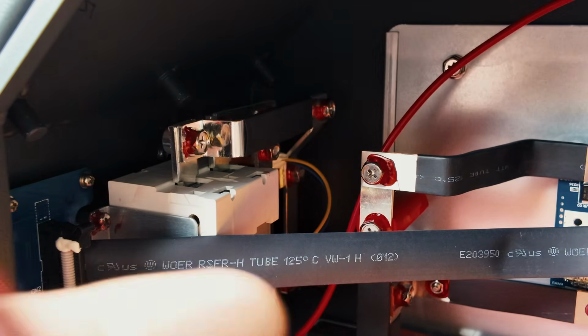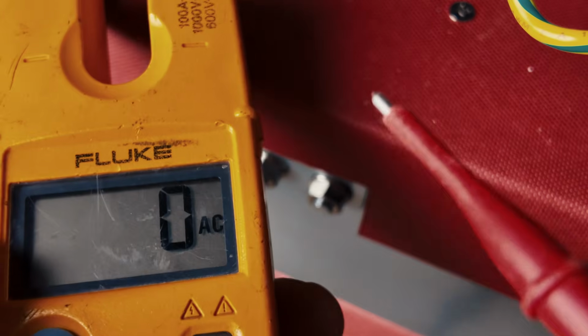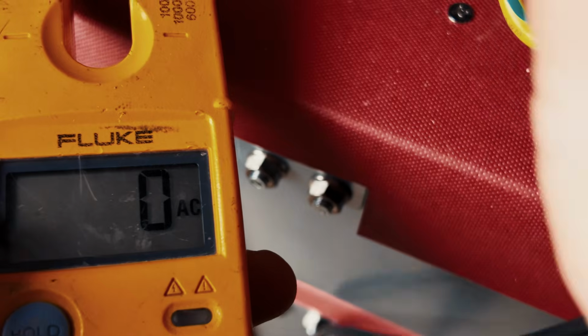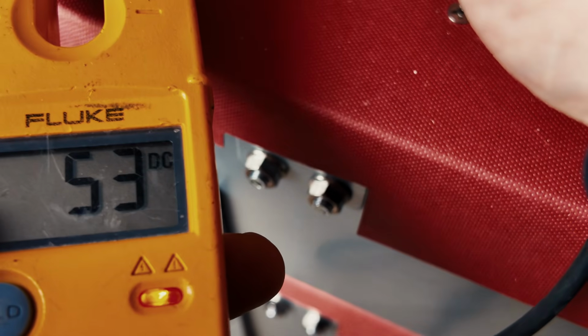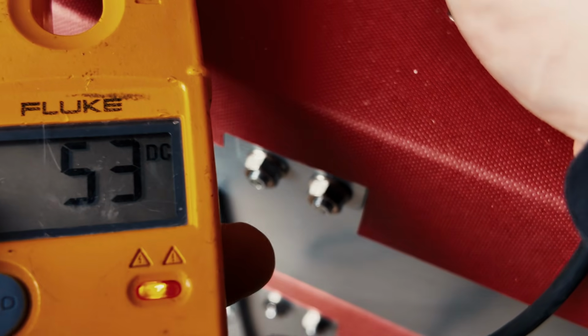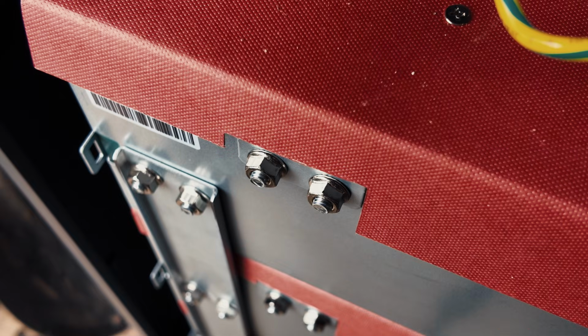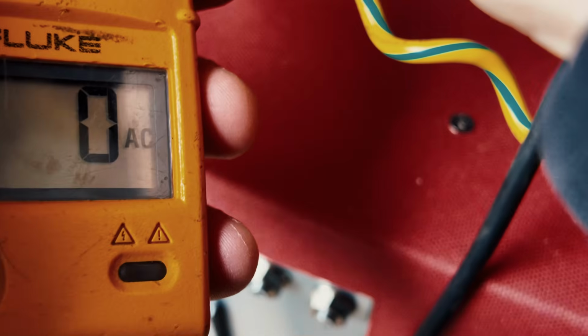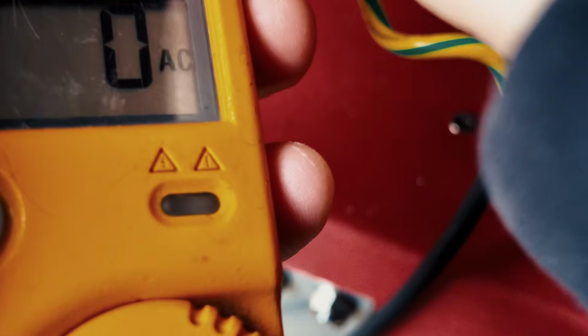There we go, 53 volts. So I'm going to try and get voltage on this now, get that on the negative, that on the positive. 53 volts there. So we've got voltage in to the MCB, and you see that. So, no volts on the outgoing supply side to the inverter of the MCB.